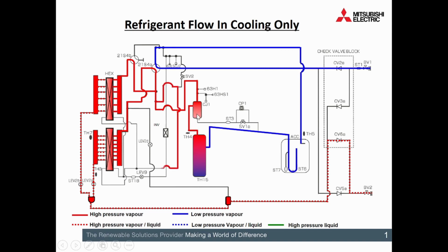Refrigerant passing from there, and it comes up to an oil separator. First 4 minutes of operation, SV1A is going to be open, so the majority of that refrigerant is going around in a little short circuit, so don't bother looking at it for the first 4 minutes. After that, SV1A will shut, and we'll use a capillary line to bring oil back from that oil separator. From there we pass up to 63HS, and we've got a pressure transducer there and a switch. So the switch is going to cut in if we see pressures in excess of 41.5 bar.